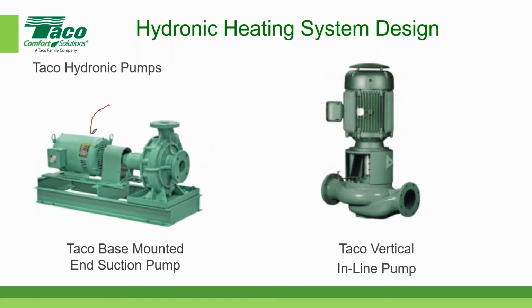So here's the motor over here, and then here is the pump. Now what you can't see, because it's covered by this cover guard here, is there are two shafts, one associated with the motor, so I'm going to make a little shaft over here at the top. There is the motor shaft, and then there is the pump shaft, and those two shafts have to be aligned with each other to within 5/1000ths of an inch. And to make the connection, there's a coupling that goes between the two.